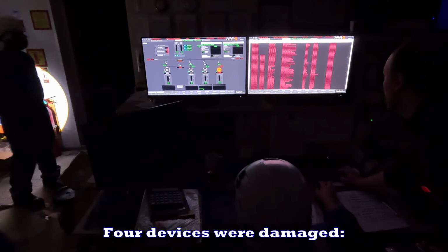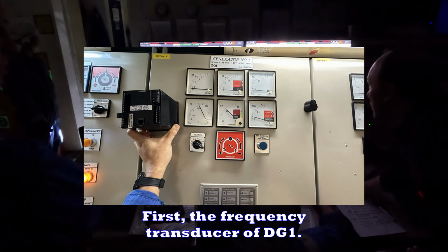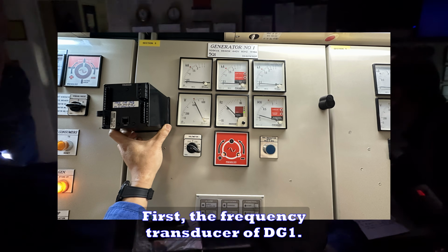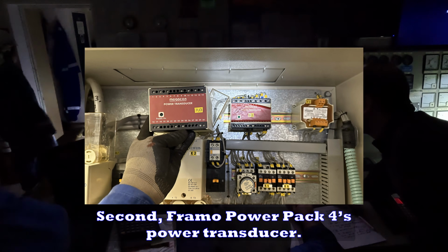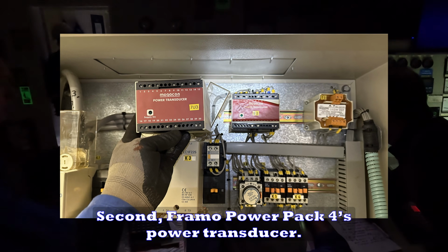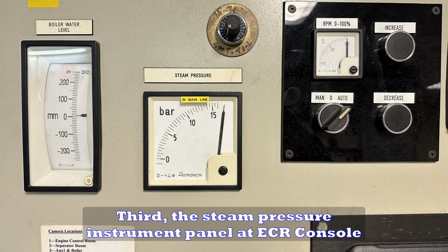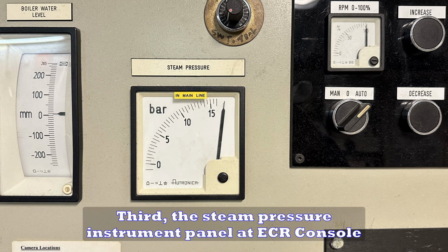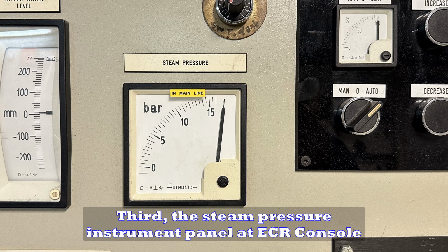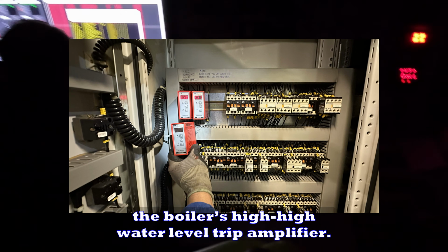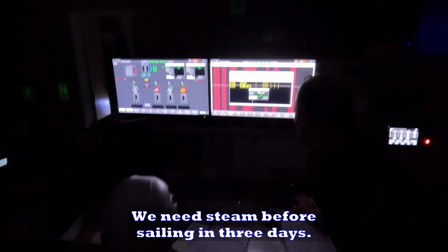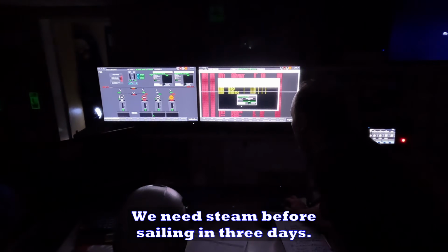Four devices were damaged. First, the frequency transducer of DG1. Second, Framo Power Pack 4's power transducer. Third, the steam pressure instrument panel at the ECR console. And fourth, a critical one, the boiler's high water level trip amplifier. That last one is non-negotiable. We need steam before sailing in three days.